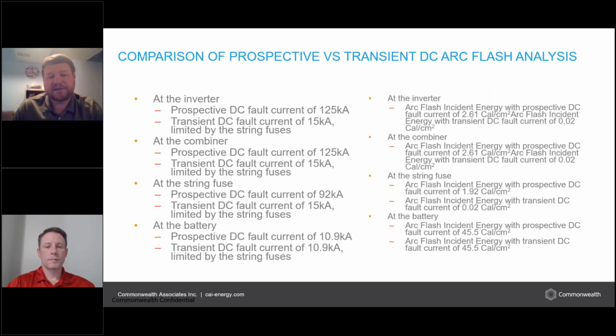So what we find is we're knocking our current from a prospective of 125 kA at some of these applications down to the 15 kA we find with that DC transient analysis that we performed. So what you can see is the direct effect of the arc flash reduction from doing the DC analysis.